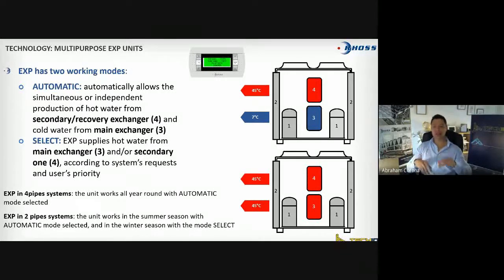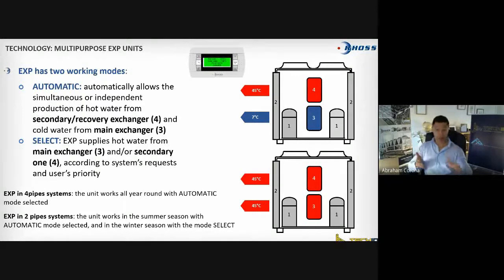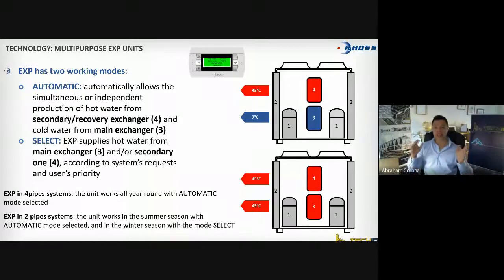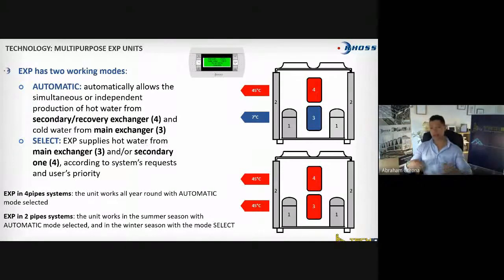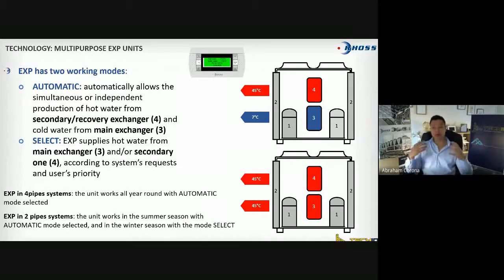You see some identification there between the main heat exchanger and the recovery heat exchanger and where the water goes. The information there is correct, of course, but it's a little bit confusing. I did something over the weekend, after I've been in the factory more than 8 times, I've been trained in this equipment, I've been working with this equipment, but every time, I don't know, the way we think in Australia, the European way is a little bit different. They are more used to saying main heat recovery, secondary heat recovery. I was getting the idea, but I was not getting the idea at the same time. I don't know if you get my point. So that is the reason, we're engineers, so I went to the basics. I asked them what is happening with the refrigeration circuit. So they showed me the refrigeration circuit.